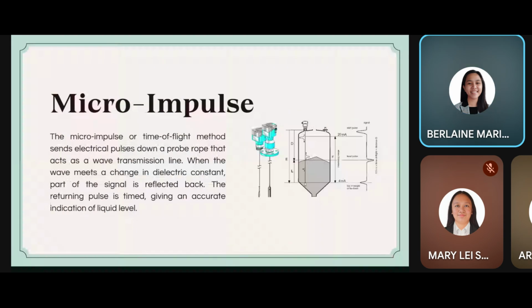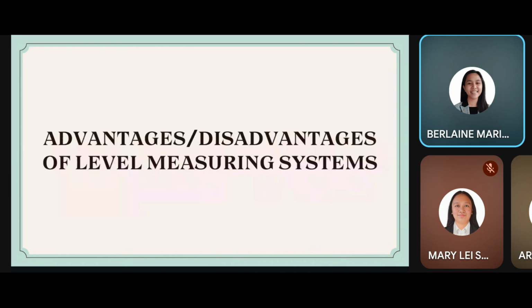Next slide po. At ang panghuli po sa inferential or indirect methods ay ang microimpulse, which is also called the time-of-flight method. It works kind of like sonar or radar, but with electrical pulses. A signal is sent down the probe inside the tank, and when it hits the liquid surface, part of it bounces back. By measuring how long it takes for the signal to return, the system can calculate the distance to the liquid level. This makes the microimpulse method very accurate and reliable for continuous measurement. Next slide, please.